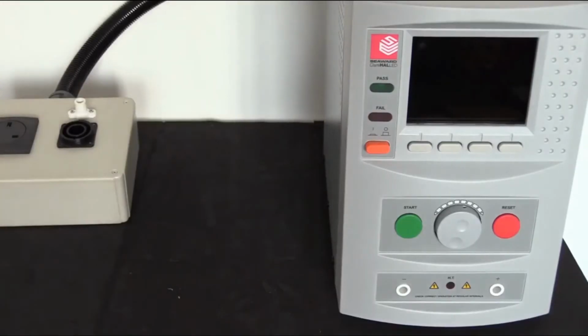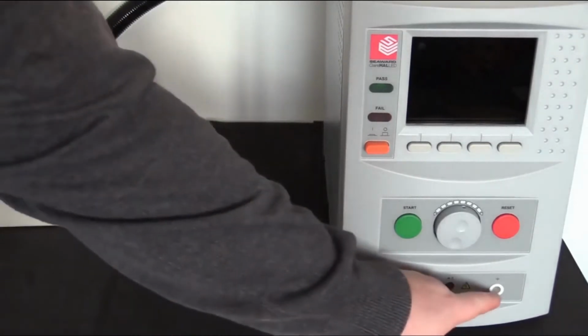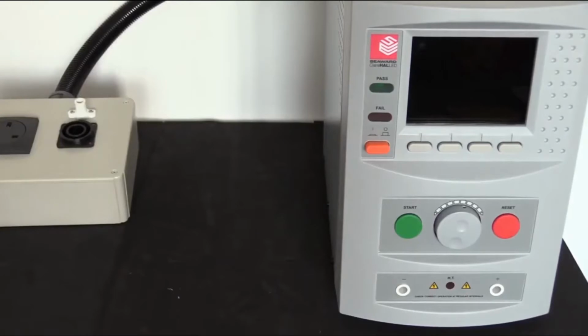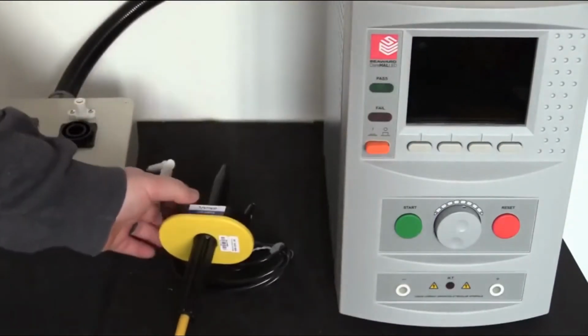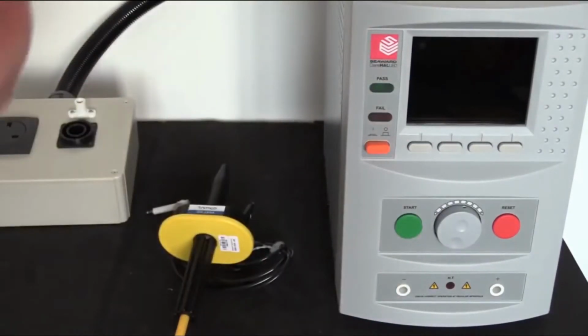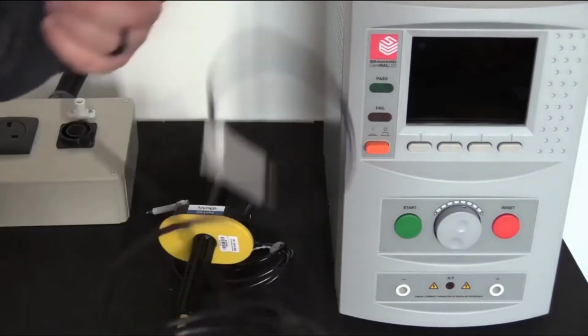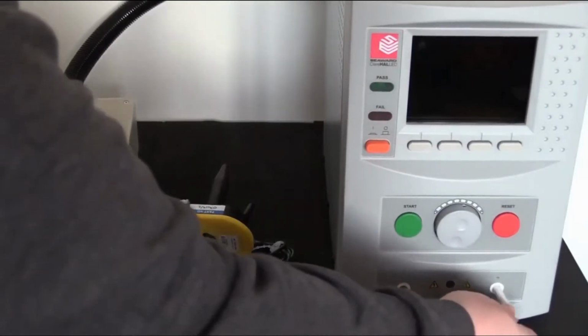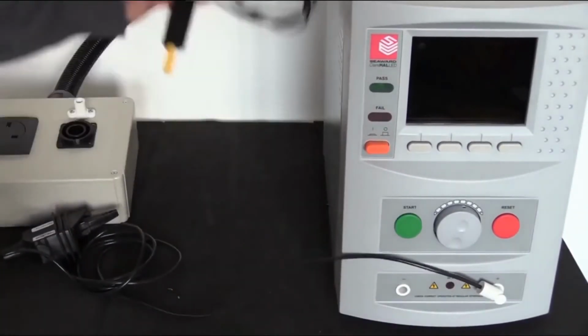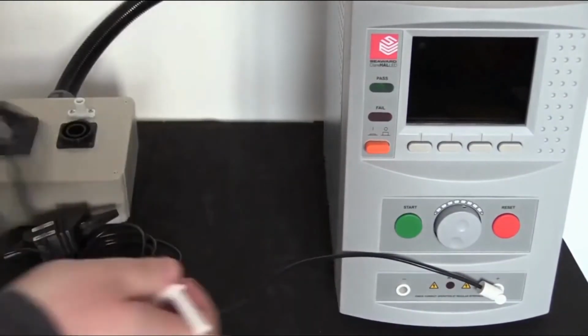In this section, we're going to talk about creating test connections when using the HAL tester. Firstly, we'll start with the HAL 101 test connections. We spoke about this earlier on in the video. We have our positive and negative outputs. So in order to make tests for HAL 101, we would simply use our Hipot return probe and our Hipot clip. Typically the best way to make the connections here would be to use your clip for the positive connection and your Hipot probe as the return.